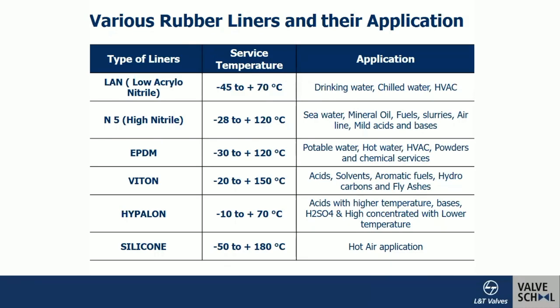The type of liner is very important for selecting the right valve. Low-acrylonitrile nitrile is the basic elastomer, especially for water service, with a temperature capability of –45°C to 70°C — suitable for drinking water, chilled water, and HVAC applications. High nitrile (N5 or high nitrile grade) has a higher temperature resistance: –28°C to 120°C, suitable for seawater, mineral oil, fuels, slurries, air line, and mild acids and bases.